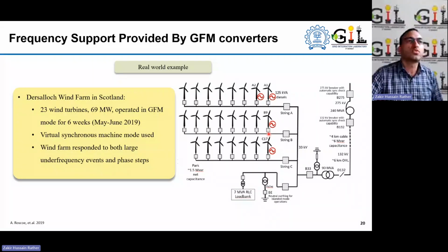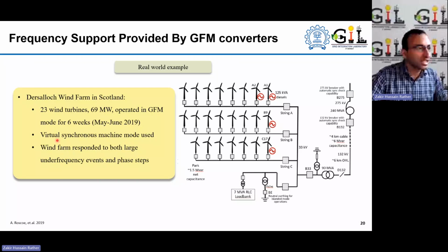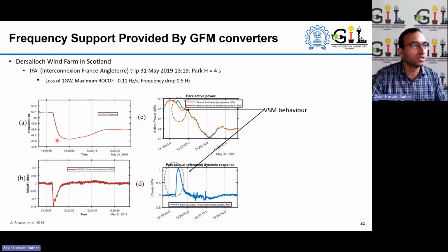If you look at the plant level, this is one of the case studies, rather a field demonstration example, where there is a 69 megawatt wind power plant operating in grid forming mode for 6 weeks, May, June 2019. And the control topology of the grid forming, as I mentioned, there are several such control topologies, that was used in this particular wind power plant is virtual synchronous machine, VSM mode. And there were naturally occurring events in the grid to which it responded. So, for example, there has been this interconnection outage, which led to around 1 gigawatt loss of in-feed, and eventually the maximum rate of change of 0.11 hertz per second in a sliding window, and the frequency deviation of 0.5 hertz at the system level. That can be seen here.